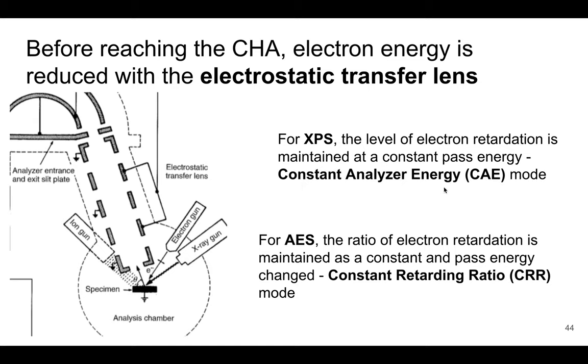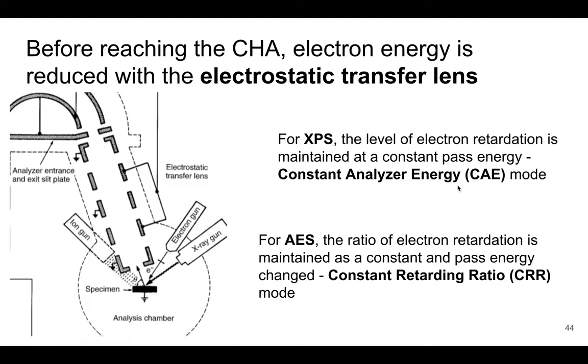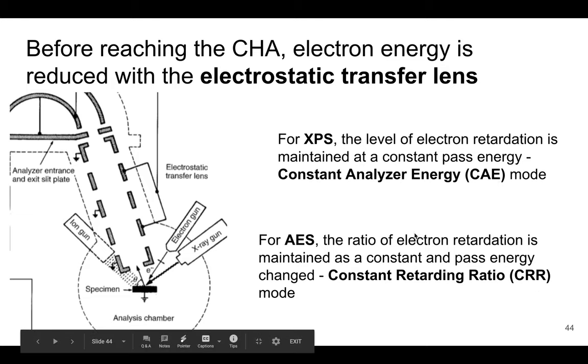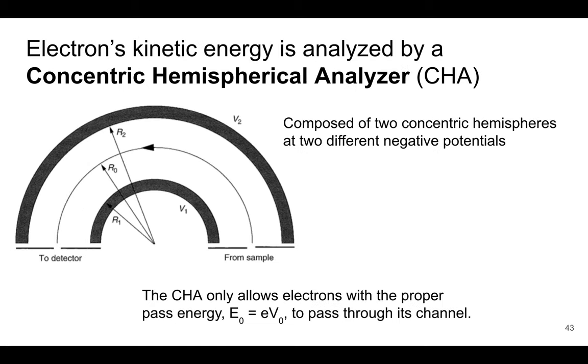For XPS, this is called constant analyzer energy mode, or CAE — maintaining the same level of retardation at a consistent pass energy. For AES, the ratio of electron retardation is maintained as a constant while the pass energy changes; this is known as constant retarding ratio, or CRR. These are the two different modes for the transfer lenses used with the hemispherical analyzer for XPS and AES respectively.